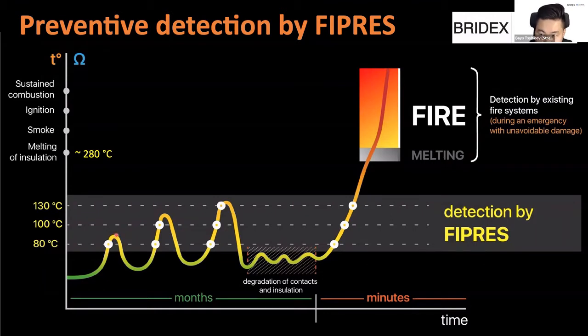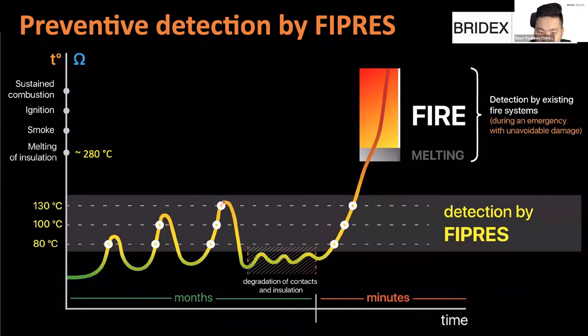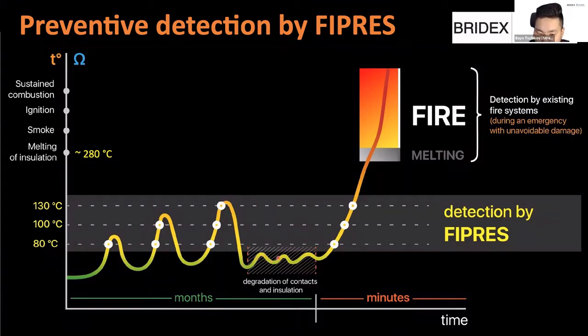When it heats up, it accelerates the oxidation process, which means the next time the overheating will be stronger, and next time it will be even stronger. This process can take several months or half a year, but at the end of the day, it will go to this stage of degradation of contacts and insulation, which means that the cable insulation is completely degraded. So breakdown voltage becomes low. The metal part of the contact is fully oxidized, and every single overheating after this stage can lead to an uncontrolled rise of temperature and then fire.